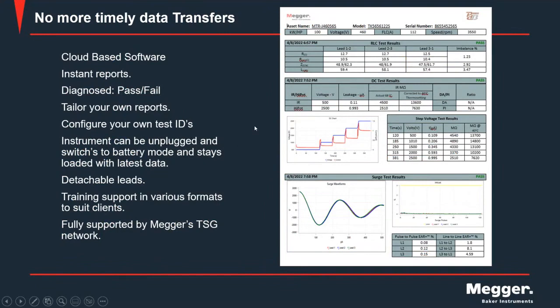The reports, like I say, are instantly created on the instrument, and it's cloud-based, so it's pass-fail. We've got pass, we've got fail. Inside the instrument, there are templates. So let's just say we've got a 460 volt machine, like in this example. Then we have a percentage of, say, 3% unbalance, which is acceptable. And then at the side here, where it says imbalance, across those results to the left, the resistance, the temperature corrected resistance and inductance and so on, impedance, sorry. And then what we've got down the bottom there is our levels of unbalance, which are pass.